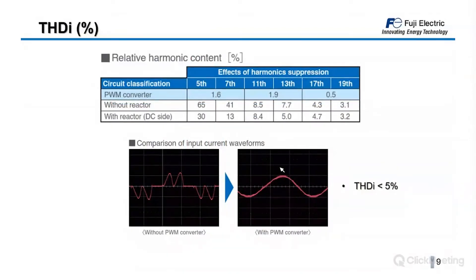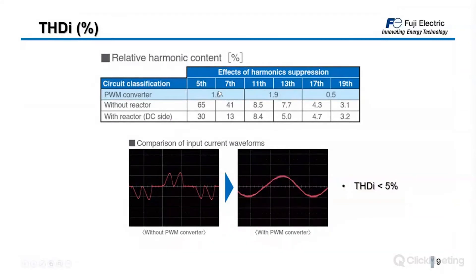Regarding THDi: when using a PWM converter ERHe, total harmonic distortion goes below 5%. By controlling the IGBTs on the ERHe, we generate an almost perfect sinusoidal wave, as shown in the image. On the left is the current waveform with a standard inverter without a reactor, and the graphic shows the harmonic level percentage for each harmonic — comparing the standard inverter case with and without reactors versus the ERHe solution.